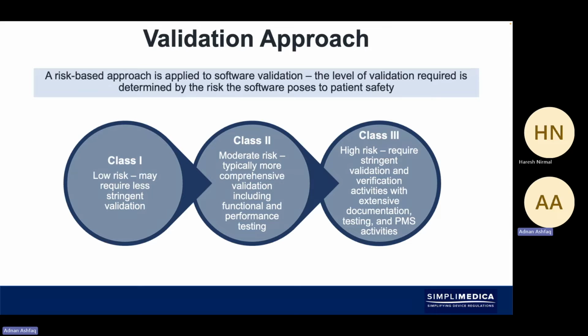So now moving on to the approach itself, because we're looking at a risk-based approach, we're looking at the classification of the medical device. So is the device class 1, class 2, or class 3? The level of validation will also be determined by the risks posed by the software within the medical device.